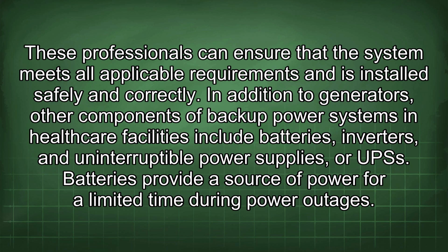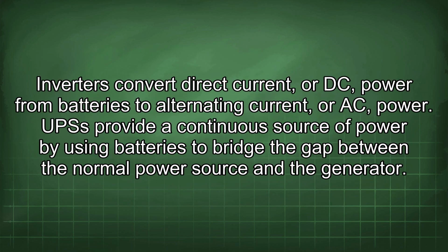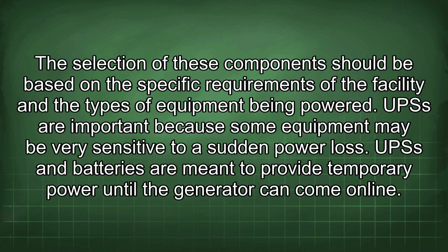In addition to generators, other components of backup power systems in healthcare facilities include batteries, inverters, and uninterruptible power supplies, or UPSs. Batteries provide a source of power for a limited time during power outages. Inverters convert direct current, or DC, power from batteries to alternating current, or AC, power. UPS provide a continuous source of power by using batteries to bridge the gap between the normal power source and the generator. Selection of these components should be based on the specific requirements of the facility and the types of equipment being powered. UPS are important because some equipment may be very sensitive to a sudden power loss. UPS and batteries are meant to provide temporary power until the generator can come online.